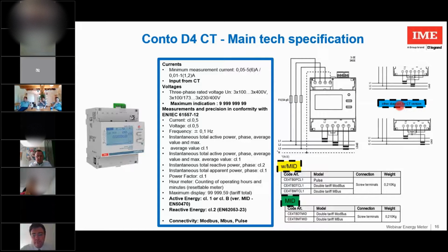If you mean you want to know when you produce or consume, you find the direction of the current through the power. On the display or via Modbus, you have a parameter, the power, three-phase or single-phase, with a sign. If you have a minus in front of the power, you produce; when you have a plus or nothing, you consume. So via Modbus you can check this parameter and act on it, for example with an interrupt, or if you know there isn't a production in these cases, you have a bad insertion.